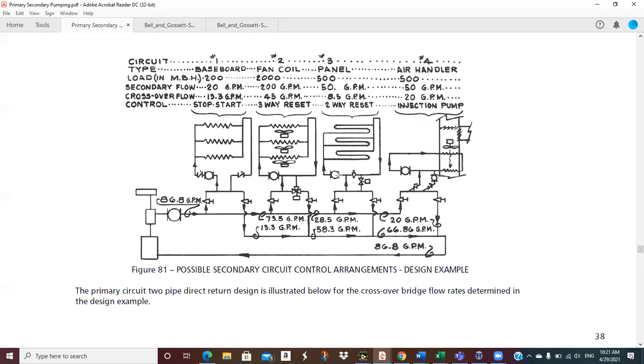The panel heating elements, we're going to do a two-way valve. I think this is just showing some different options here. Where we got our balance valve here, opens up. Going to pump this continuously. And then here's my air handler control over here. So that's going to be an injection pump. So we'll put shots of heat up here into this secondary loop when we need it. And then the injection pump will start and stop, and the secondary pump will go continuously.